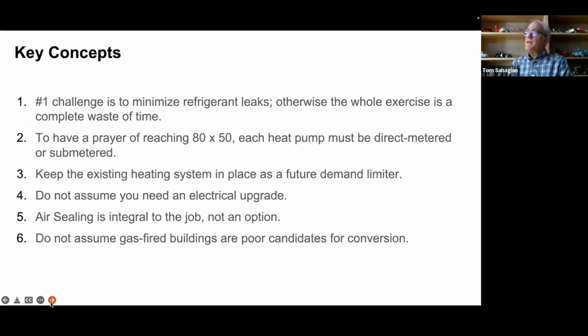Another key item is that a lot of buildings thinking about changing their systems have the idea that they want to also get rid of the old heating system. Personally, I think that's a mistake, because I think what's going to happen in the future, as more and more buildings convert to heat pumps, is Con Ed's peak demand period will shift from the summertime to the wintertime. Just like they do now, they will pay users to reduce their peak demand on the coldest days, so they don't have to increase the size of their system. So I like the idea of using the existing heating system from time to time on the coldest days of the year as a demand limiter.